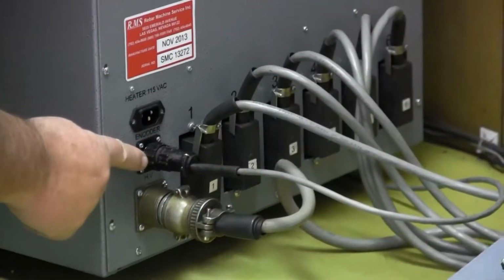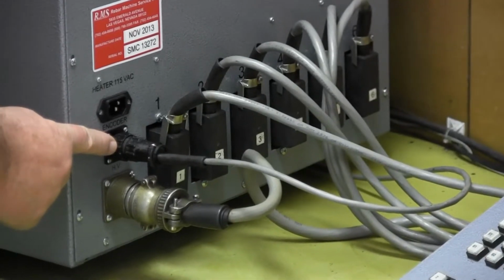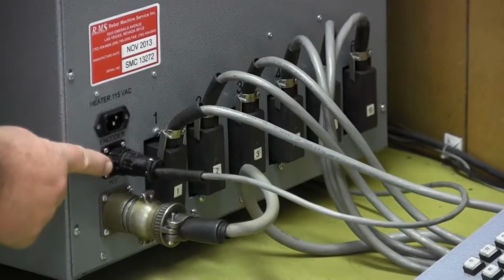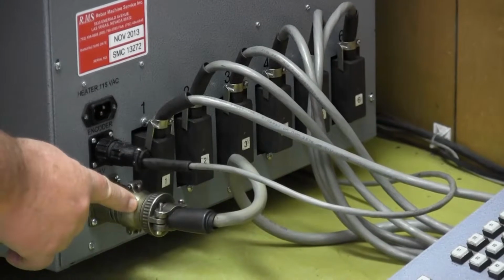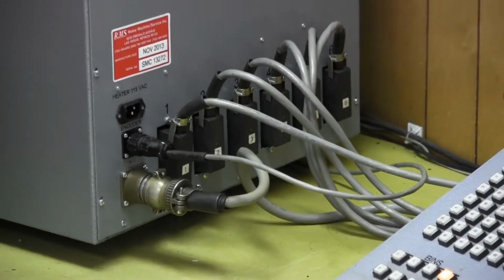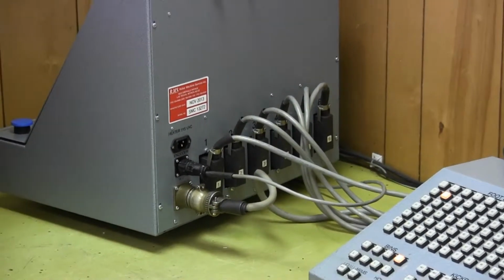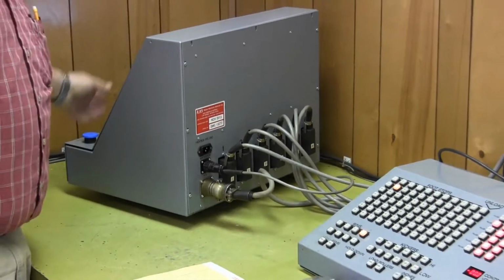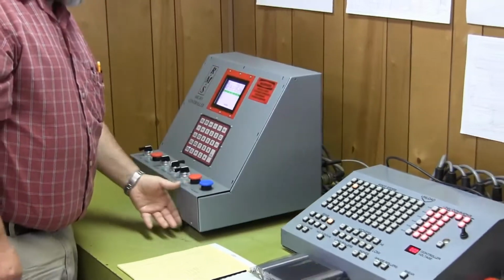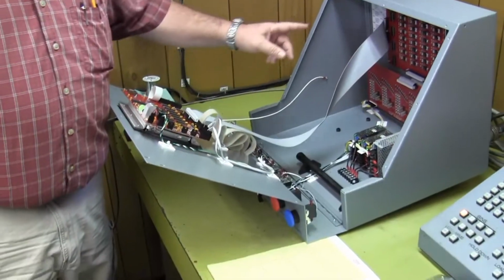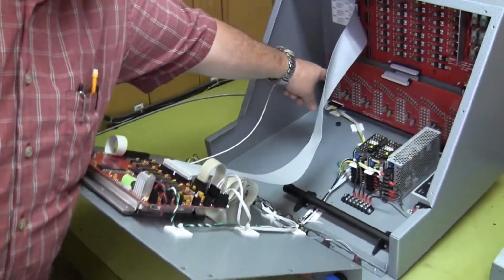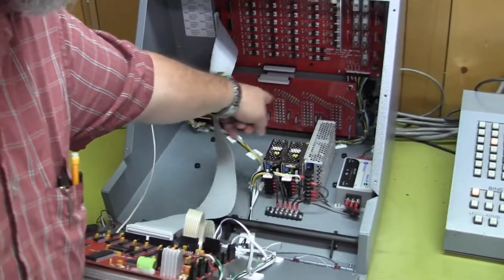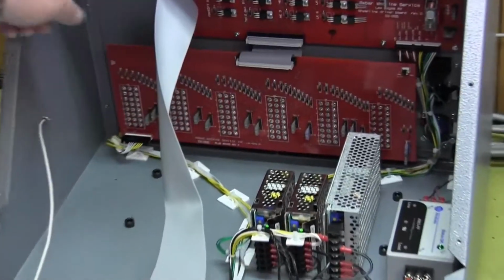The encoder plug gets your encoder signal, and that works with the inches. And then you have a high voltage plug that handles the load rollers, gauge rollers, inches, and the shear, the shearing. We have a plug board. That's where the plugs plug in, and it's fused. And there's a fuse chart here. So it shows you which.